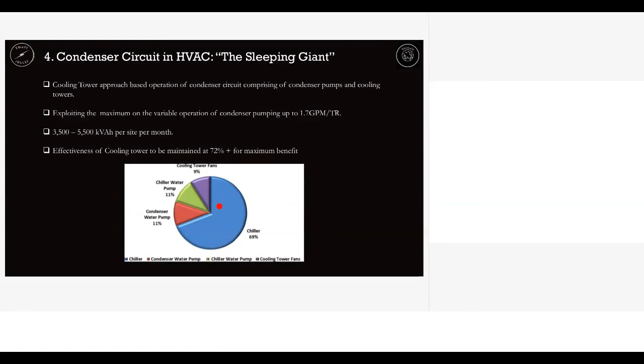So that I am able to be heard properly. Our point is the centralized air conditioning. This is the percentage sharing, or the consumption sharing, in the plant room. So chiller is the most, pumps are second, and cooling tower fans are third. As I told, the objective is to save energy from the system. This is one of the points that we introduced, and it has 3 parts. So you should understand, one is the blue line.